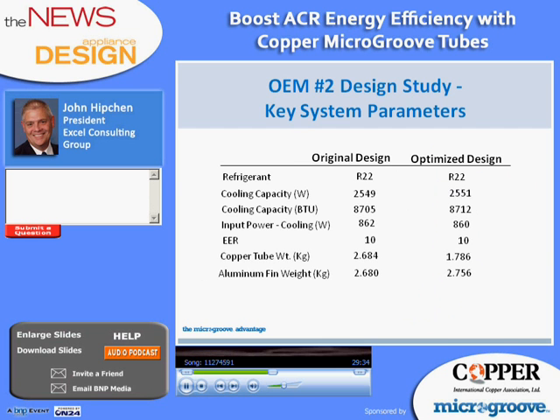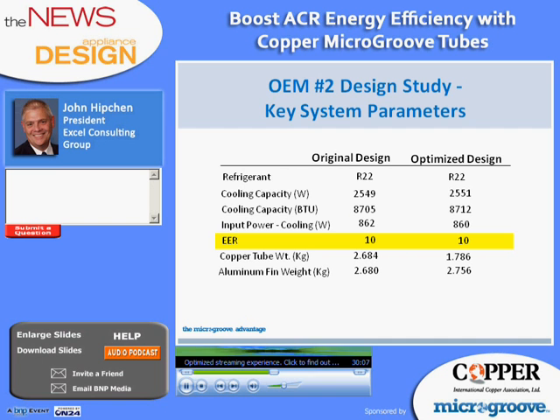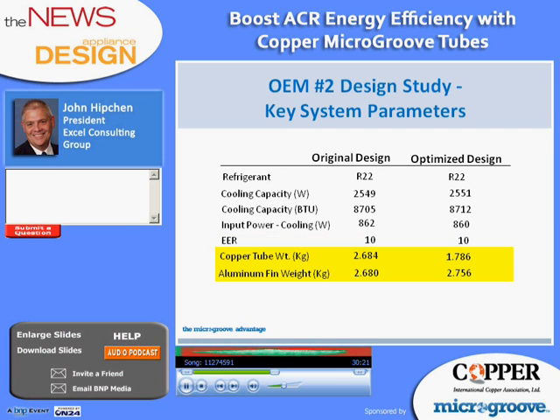Let's look at OEM number 2. And that's what we've got now. And we're looking at a completely different system here. But we're looking for the same type of competitive edge with this optimized design. So we will run through this data just as we did for OEM number 1. Compared to OEM number 1, we have a slightly lower cooling capacity, but considerably more input power. So we see a lower EER of 10 compared to the EER of 12 that we had with OEM number 1. So this system would not qualify for the Energy Star certification.